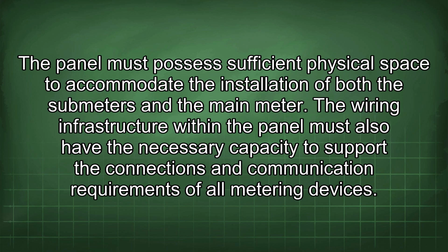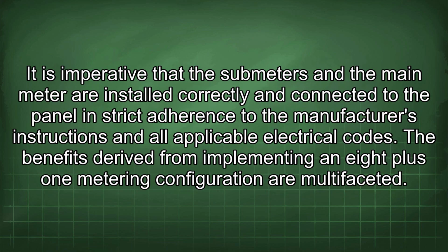The wiring infrastructure within the panel must also have the necessary capacity to support the connections and communication requirements of all metering devices. It is imperative that the submeters and the main meter are installed correctly and connected to the panel in strict adherence to the manufacturer's instructions and all applicable electrical codes.